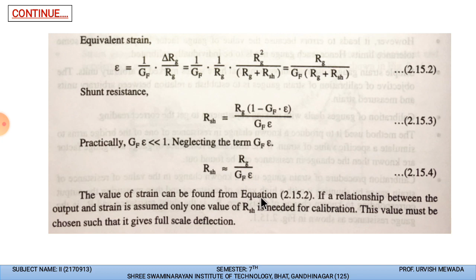Here we can consider that RSH is inversely related to the strain, so the value of the strain can be found with the help of this equation. If a relationship between the output and strain is assumed, only the value of RSH is needed for calibration. So we need to check the value of RSH while we calibrate the strain gauge, and this value must be chosen such that it gives the full scale deflection, so that we can calibrate the strain gauge easily and properly.